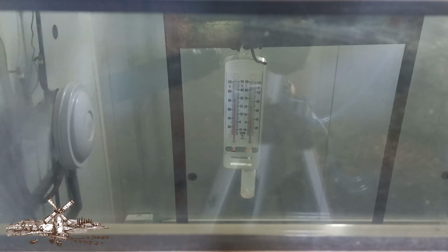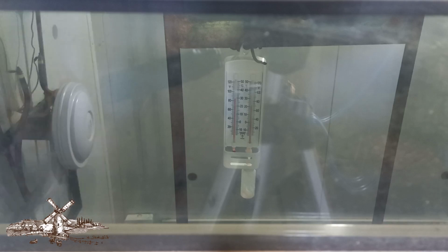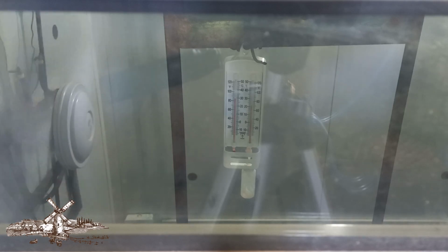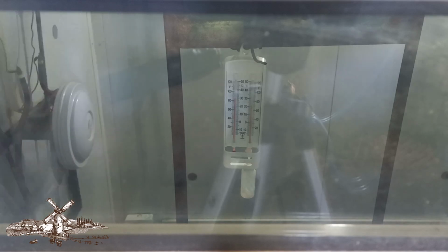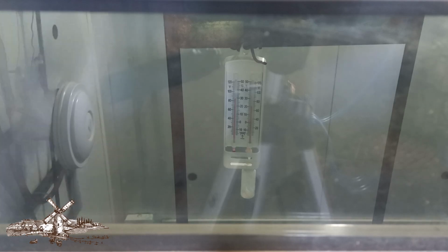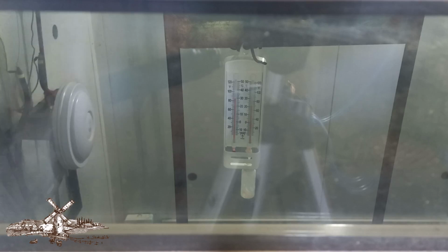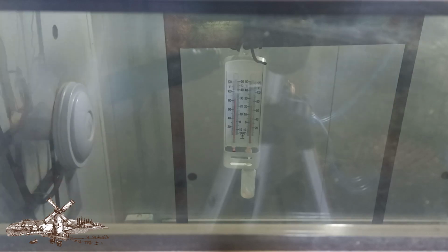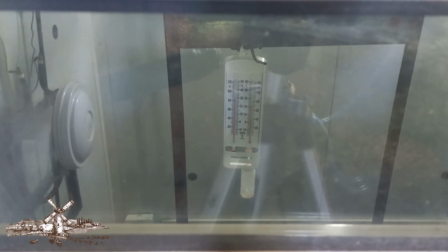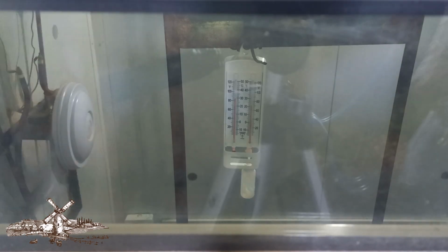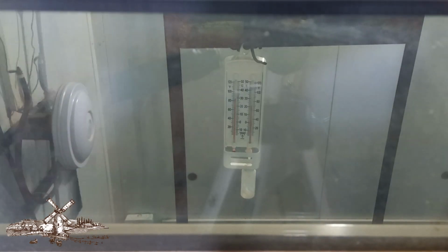Now, a wet and dry bulb thermometer like this, on the other hand, gets calibrated at the factory, and unlike our digital controllers, they are not prone to drift. So where your digital controller loses accuracy with age, your alcohol thermometer will not. And so we can accept any measurements coming off an alcohol thermometer such as this as being reliable and accurate, and we will use those as the numbers which we will calibrate our controller to.